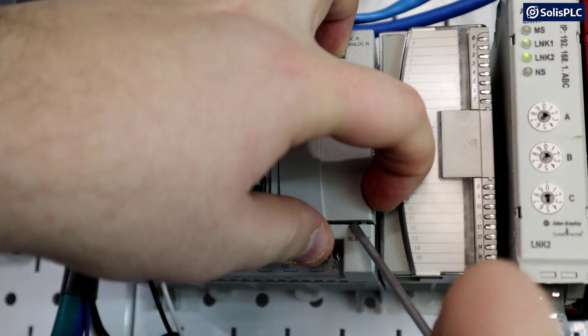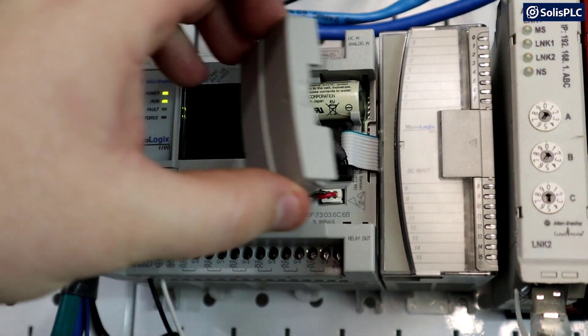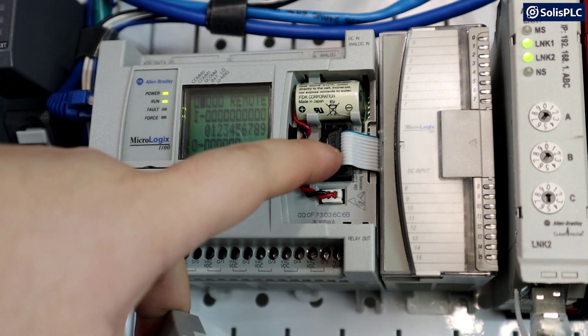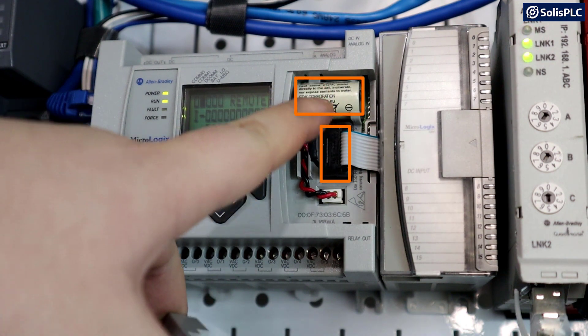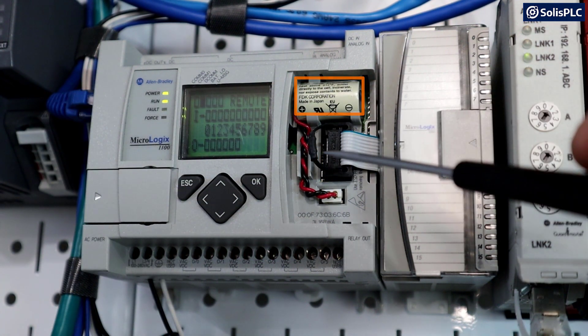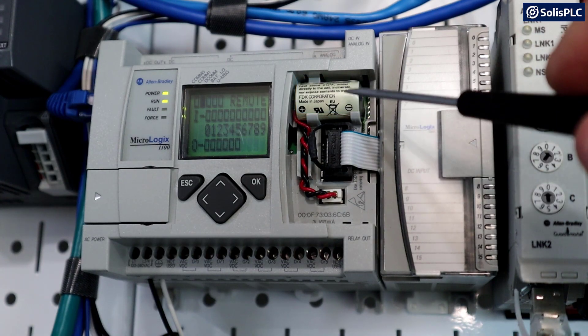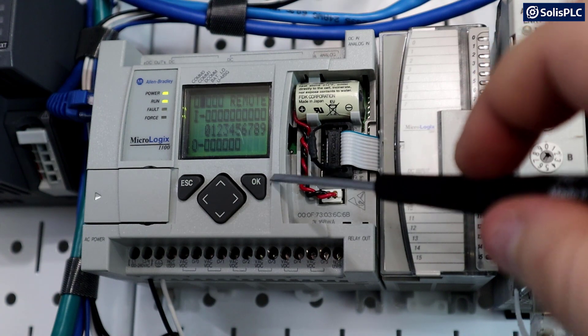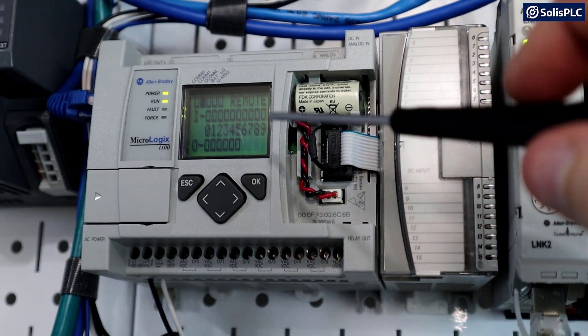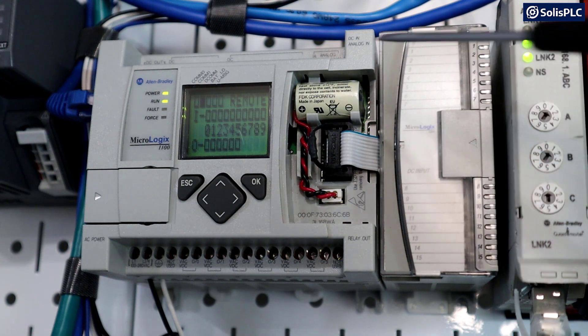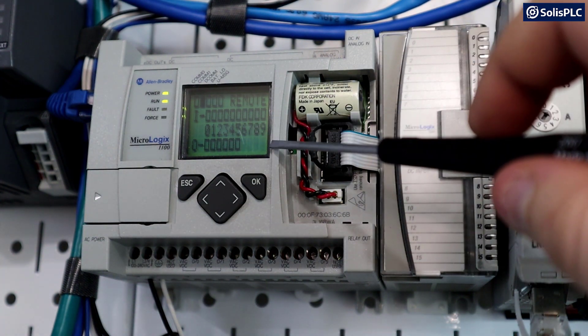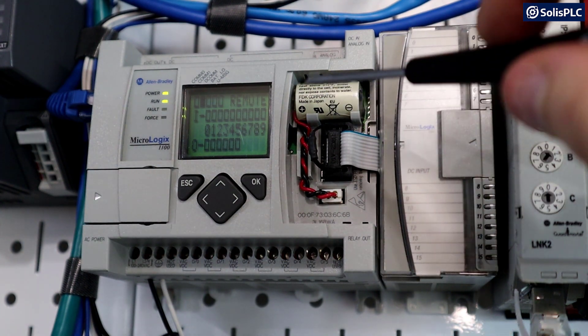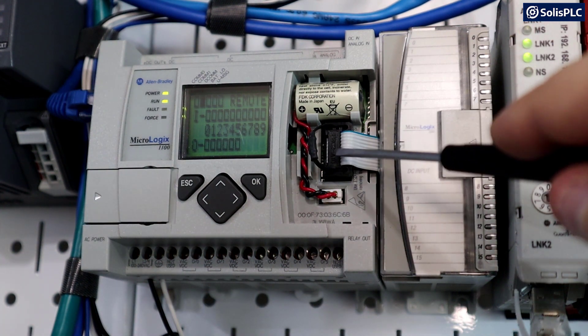I'm struggling just a little bit because I'm also standing behind the camera. But ultimately, once you remove this faceplate, you'll notice that there's going to be the ribbon cable as well as the battery. A couple of you on the side note have been asking, why is your PLC losing the IP address? Typically that's because your battery is no longer good. What happens with these older type PLCs is the IP address is stored in volatile memory that is being backed up by the battery. So as long as the battery remains in place, the IP address is going to be stored. Once the battery runs out, it's going to lose that IP address.